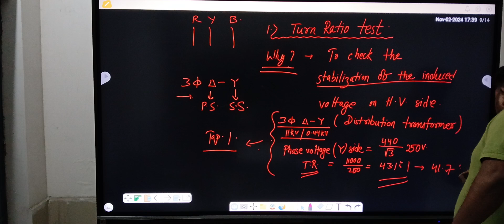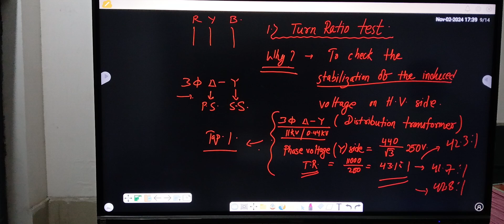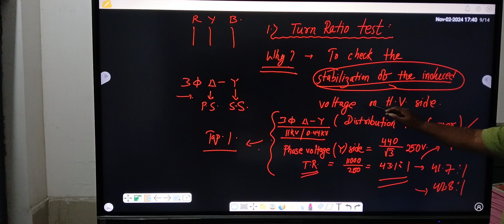Suppose we are getting a value for tap 2, that is 41.7 is to 1. Okay, no problem. Suppose for tap 5 we are getting 42.8 is to 1. No problem. Suppose for tap 16 or 17 whatever, we are getting again 42.3 is to 1. No problem. Exactly nearer value can be considered. It is not hard and fast that we will be getting 41.7 is to 1 only in each and every tap, but the nearer value is considered. Then only we can say that the turn ratio or the voltage ratio of the transformer is successful and the transformer is healthy in terms of stabilization of the induced voltage. Is that clear?